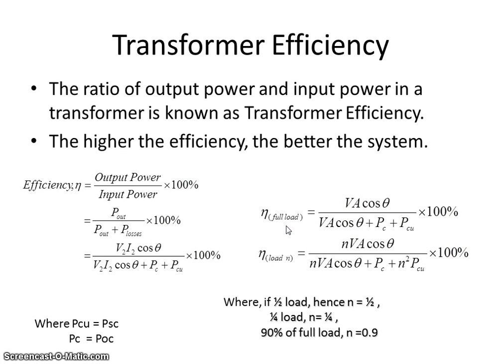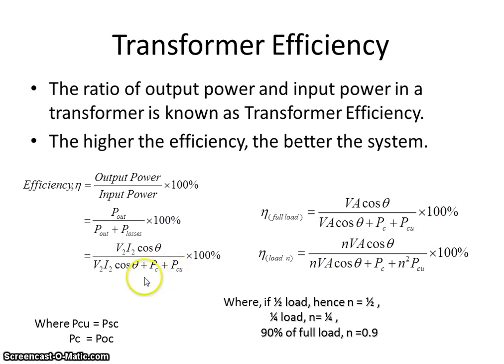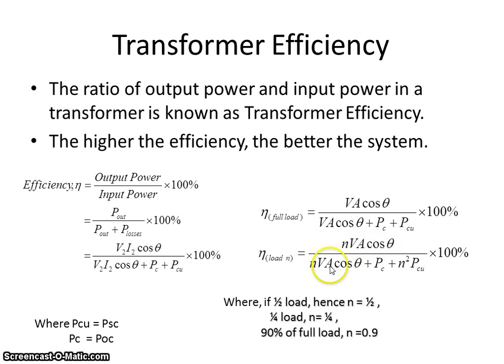Coming to transformer efficiency: the ratio of output power to input power in a transformer is known as transformer efficiency. The higher the efficiency, the better the system. The efficiency formula is output power divided by input power, expressed as a percentage: η = P_out / (P_out + losses) × 100%. That is, η = V2·I2·cosθ / (V2·I2·cosθ + PC + PCU) × 100%, where PC is the core loss and PCU is the copper loss. Full load efficiency: η = VA·cosθ / (VA·cosθ + PC + PCU). Efficiency at partial load: η = N·VA·cosθ / (N·VA·cosθ + PC + N²·PCU).